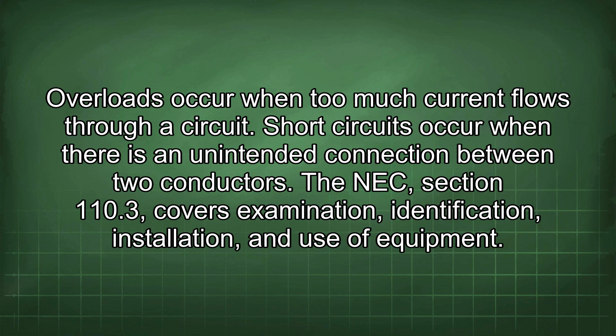The NEC Section 110.3 covers examination, identification, installation, and use of equipment. This section requires that electrical equipment be installed and used in accordance with the manufacturer's instructions. It also requires that the equipment be properly identified and marked. The NEC Section 210.12 addresses arc fault circuit interrupter protection, known as AFCI. AFCIs are used to protect against arc faults, which are dangerous electrical faults that can cause fires. AFCIs are required in many areas of the home, such as bedrooms and living rooms.